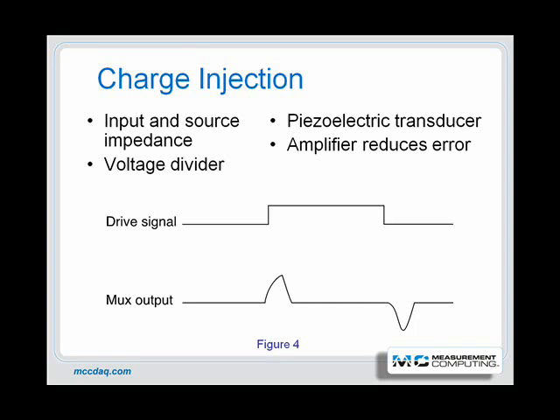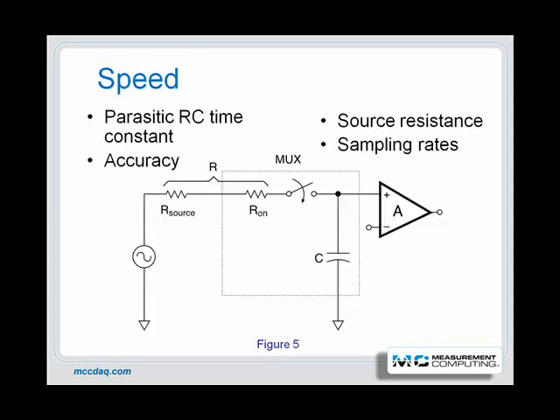Channel-to-channel crosstalk is another non-ideal characteristic of analog switching networks, especially integrated circuit multiplexers. Crosstalk develops where the voltage applied to any one channel affects the accuracy of the reading in another channel. Conditions are optimum for crosstalk when signals of relatively high frequency and high magnitude, such as 4 to 5 volt signals, are connected to one channel, while 100 millivolt signals are connected to an adjacent channel. High frequency multiplexing also aggravates crosstalk because signals couple through a small capacitance between switched channels. Low source impedance minimizes crosstalk and eliminates charge injection.